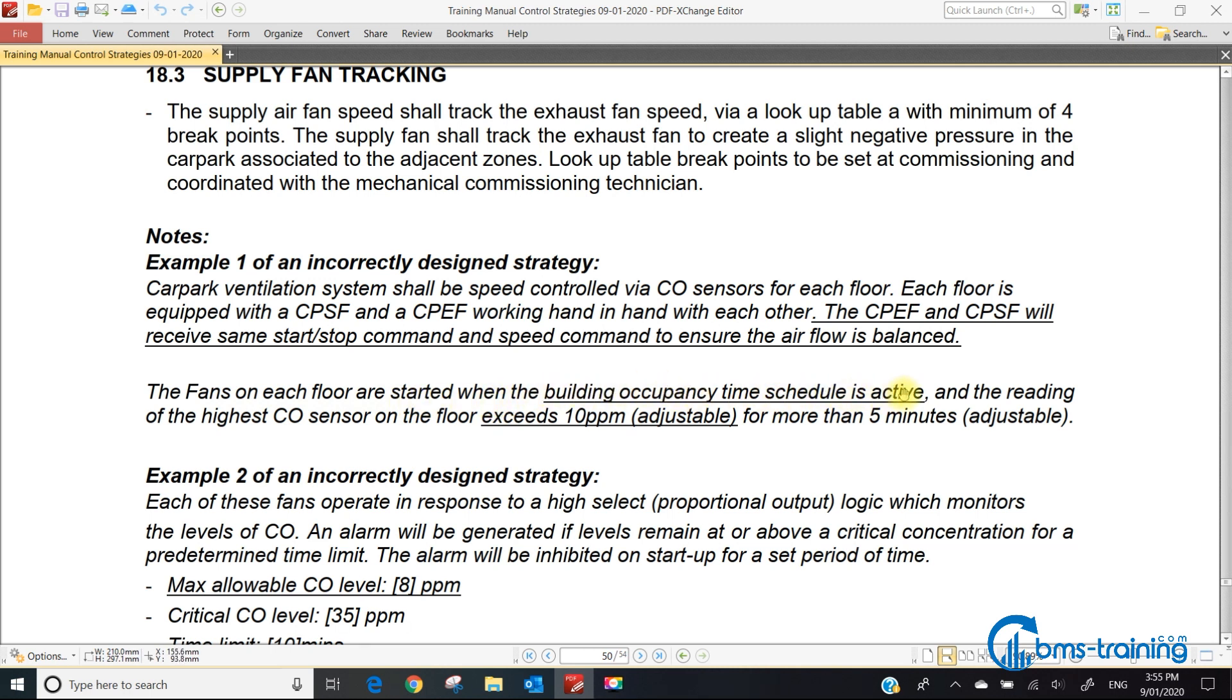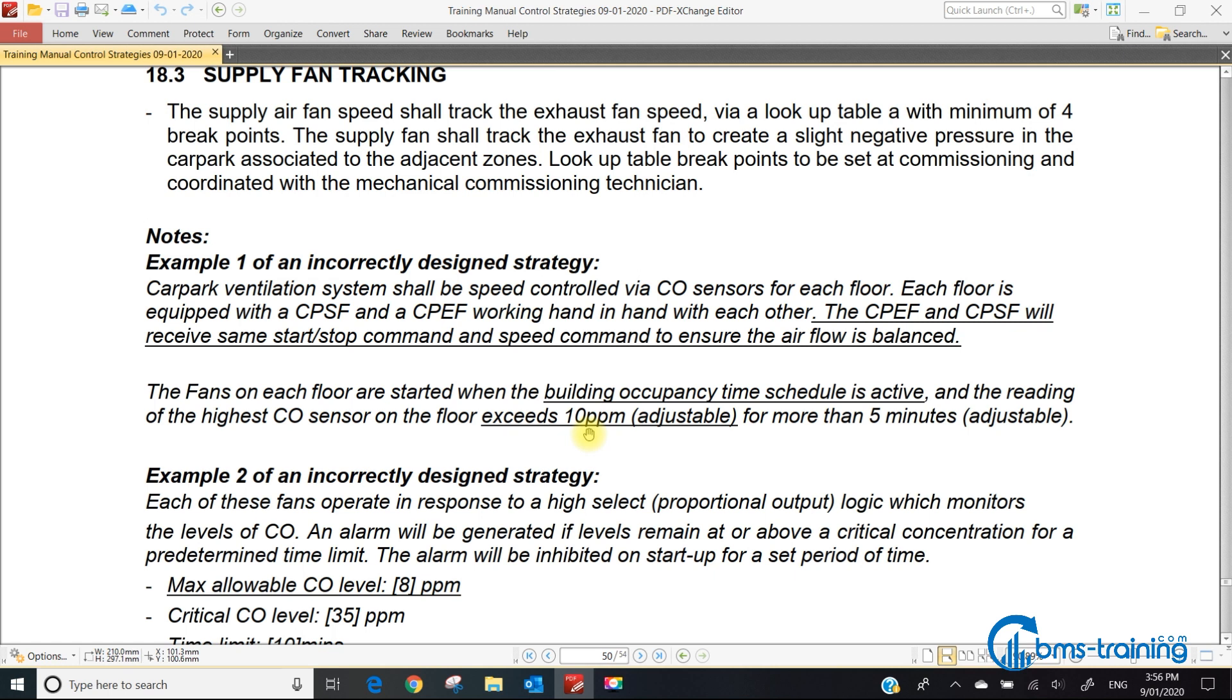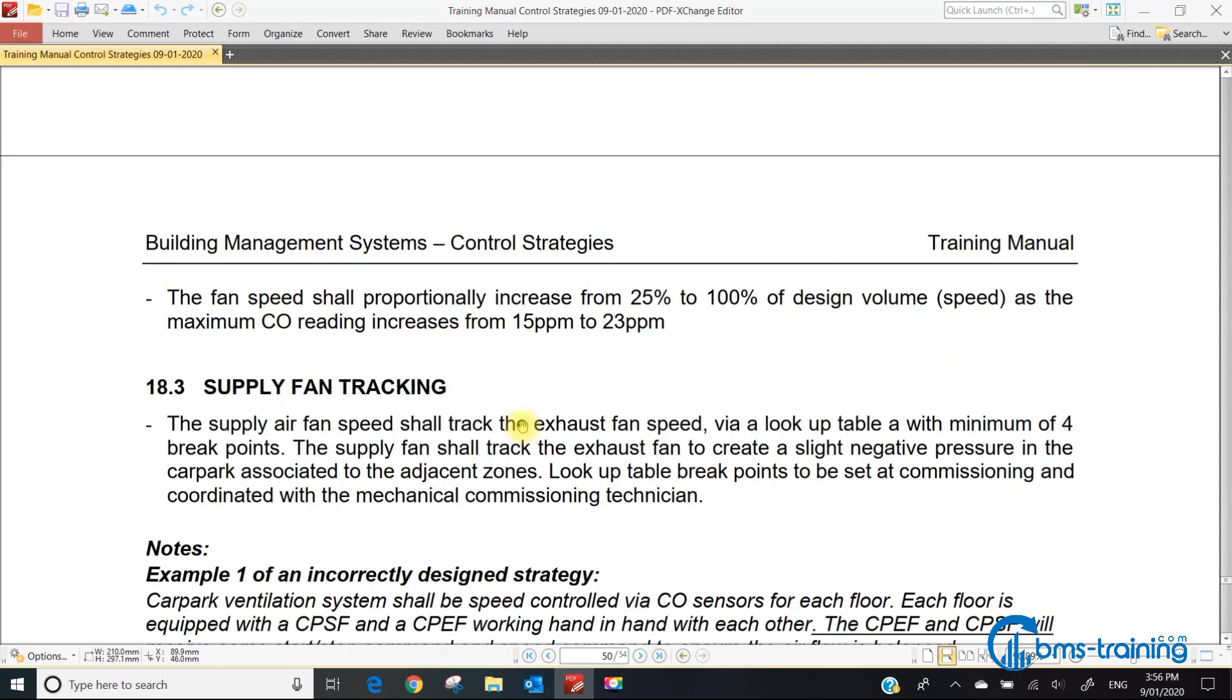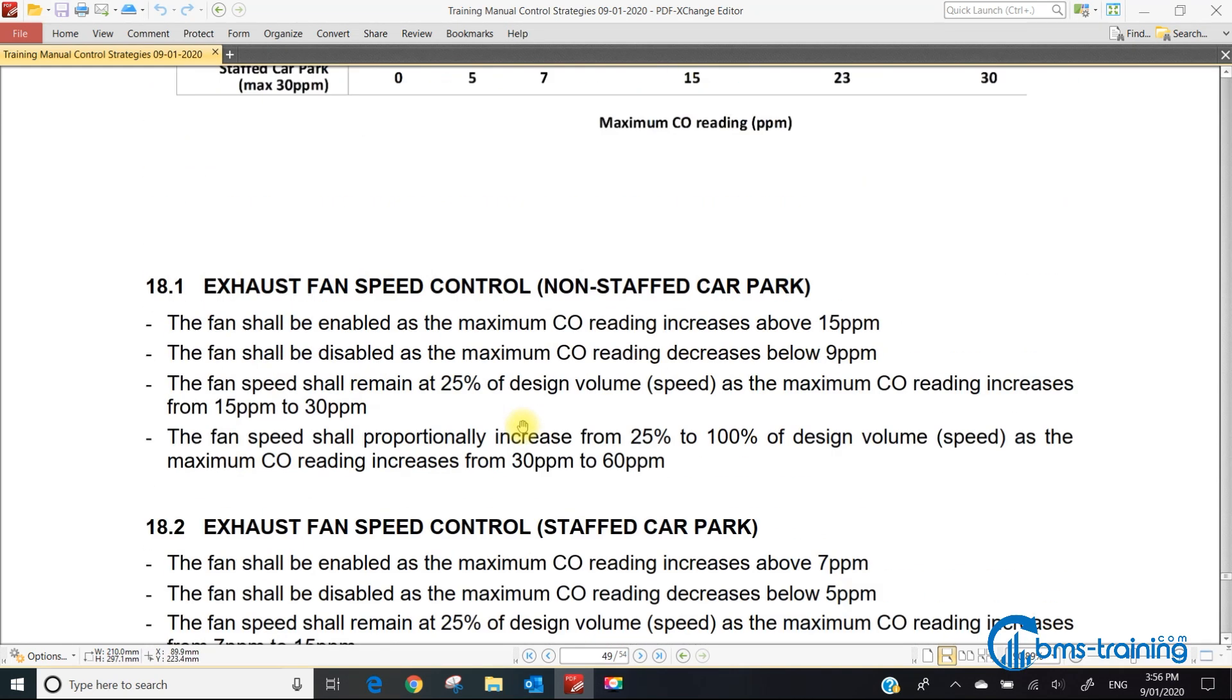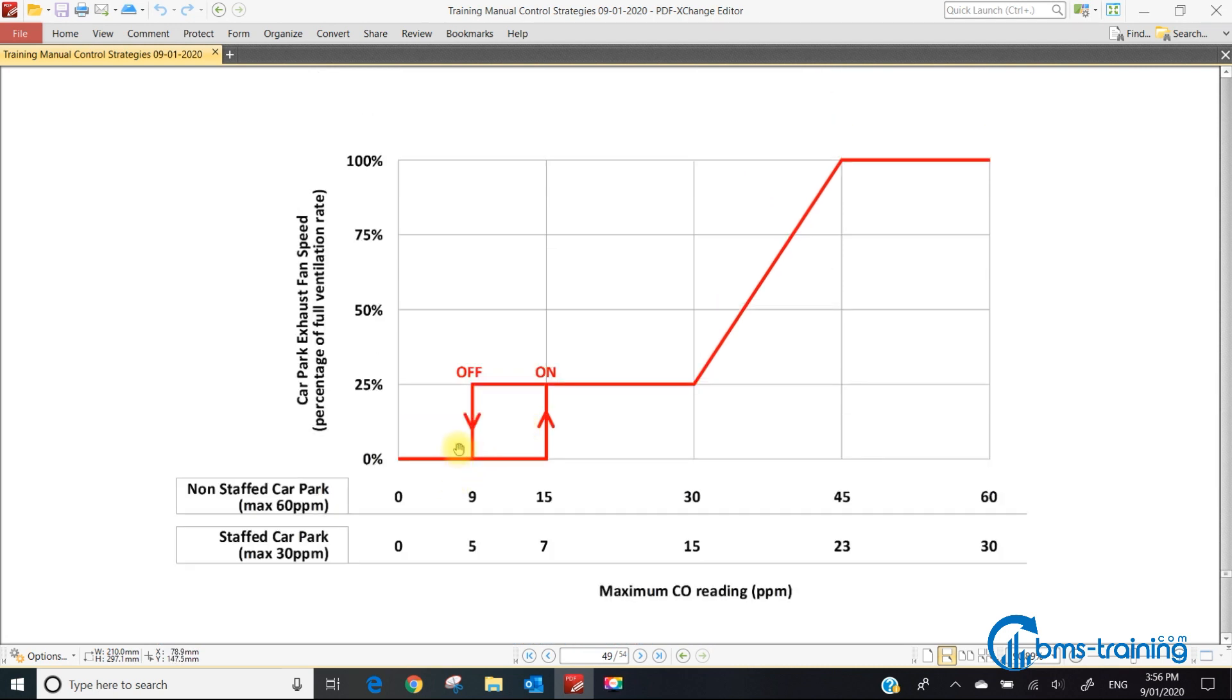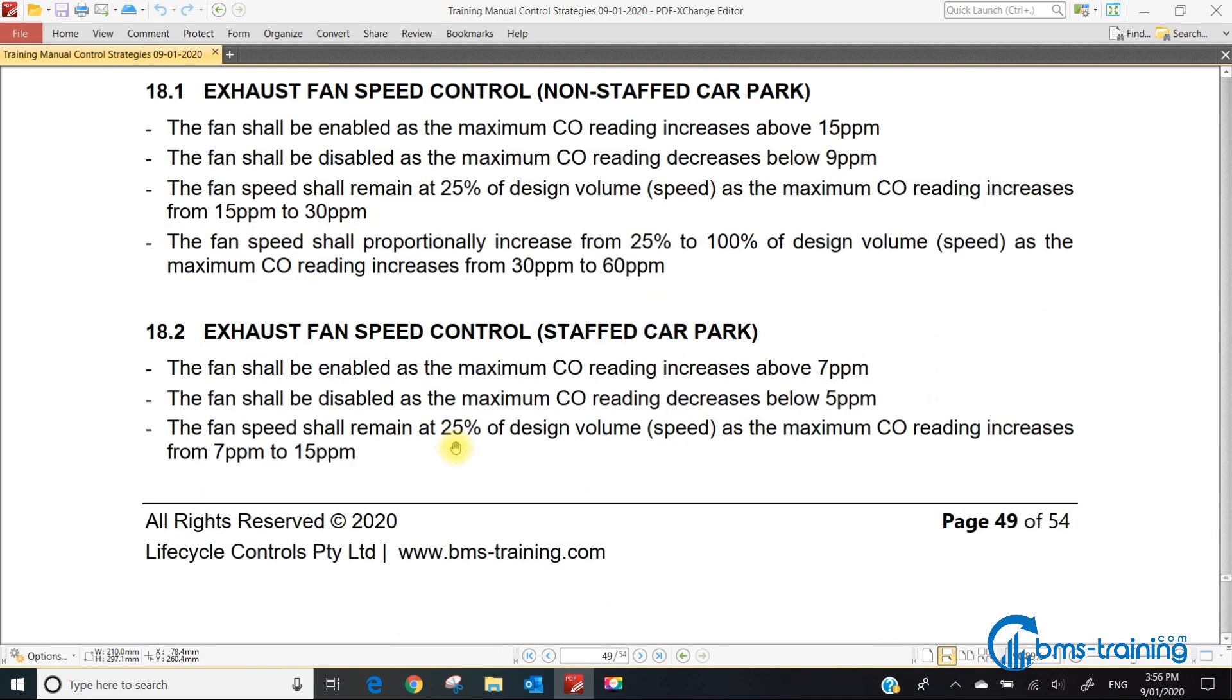Here are examples from FDs. The first one says the car park exhaust fan and supply fan receive the same start-stop and speed command to ensure airflow is balanced. They should not get the same speed command. Worst case, the supply fan should track the exhaust by 90% so you're always exhausting more air. That same FD said fans start when the building occupancy time schedule is active, but we shouldn't have a time schedule.